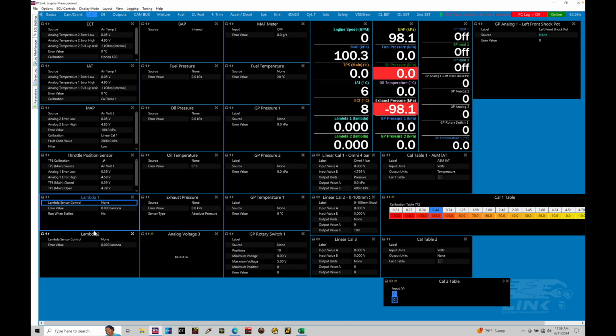One thing I want to mention is something called a voltage offset. Once we've programmed and set up everything for the analog type of input, there's a possibility that if you compare what your gauge reading shows to what the link actually shows, there might be a discrepancy. That's the voltage offset — the gauge broadcasts a certain voltage, but there's a slight deviation when that voltage comes into the link. This is something we often can't fix, so just be aware there may be a slight discrepancy between your accurate gauge reading and what you see coming into the link.